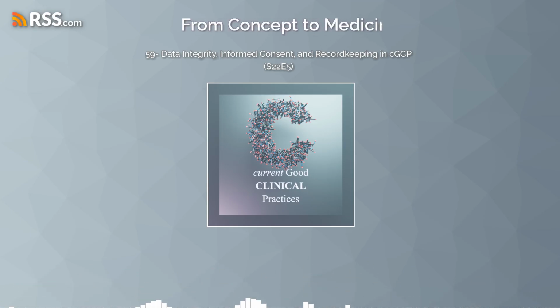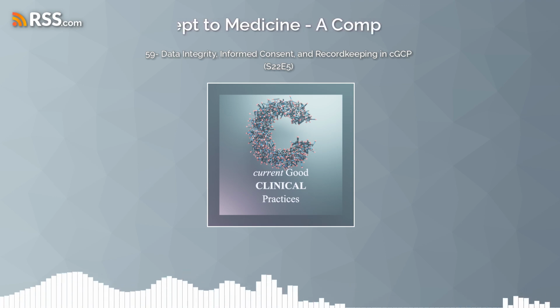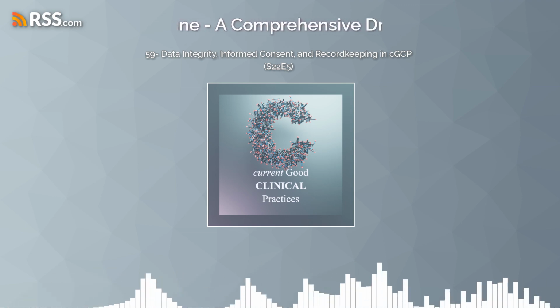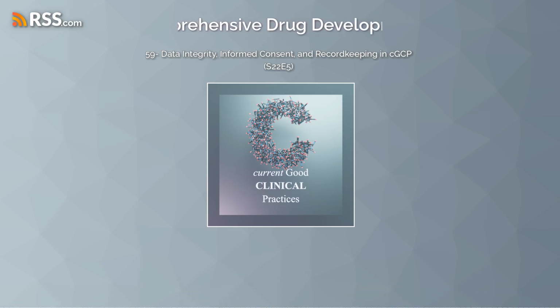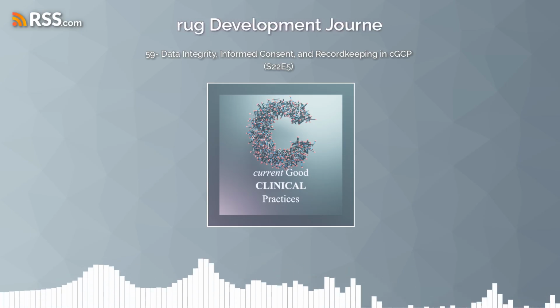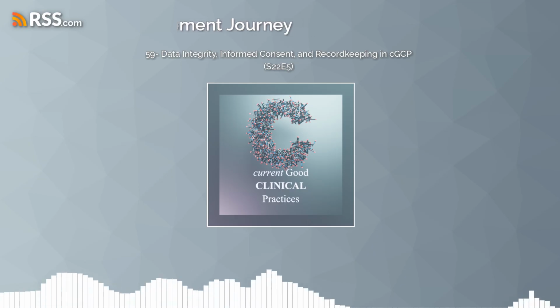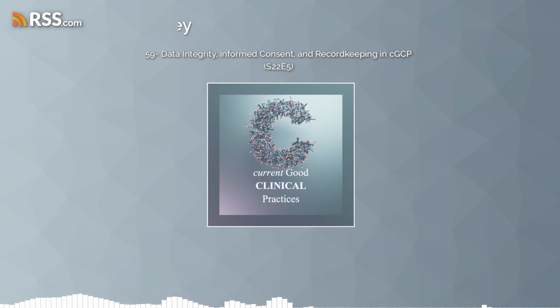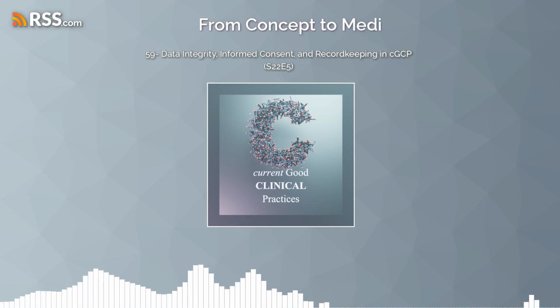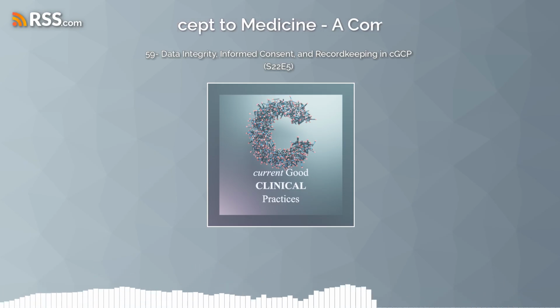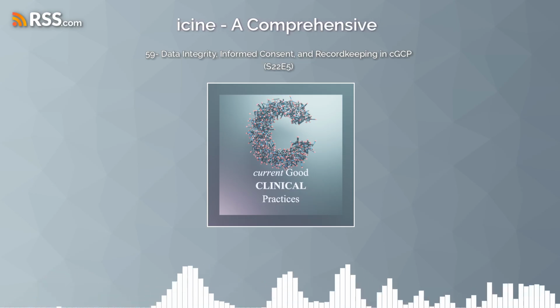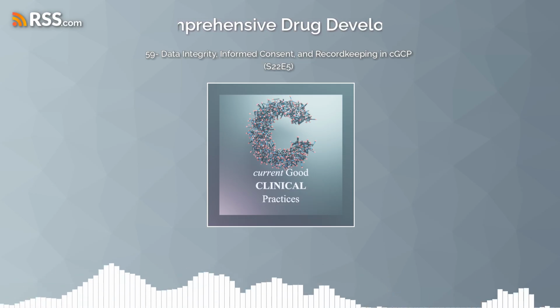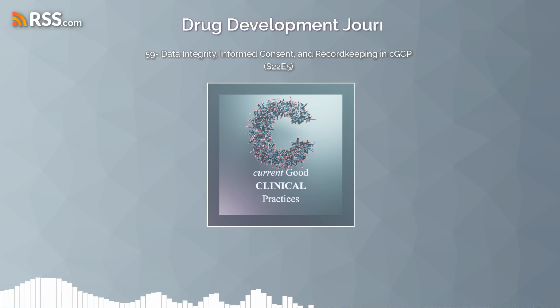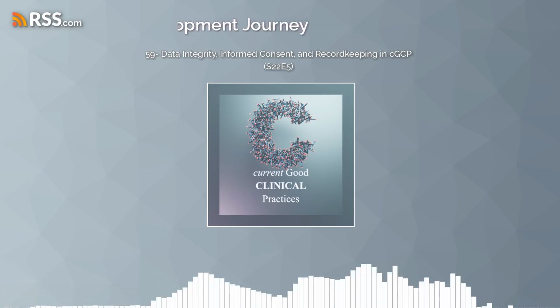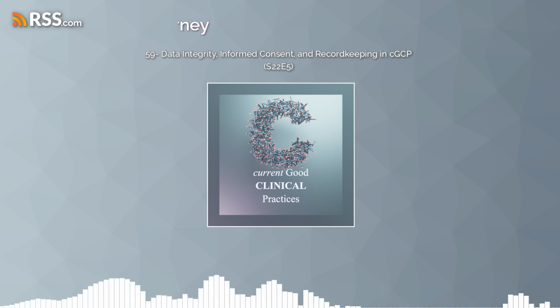I've heard the term equipment qualification thrown around quite a bit. DQ, IQ, OQ, PQ. That whole alphabet soup, what is that all about? So you can think of it as building documented confidence in the equipment at each stage of its life. As EAS Consulting Group explained, design qualification, or DQ, is basically confirming that the equipment is designed to meet the specific requirements and regulations. So it's designed right from the start. Exactly. And then installation qualification, IQ, verifies that the equipment is actually installed correctly, following the manufacturer's specifications. Exactly, by the book.